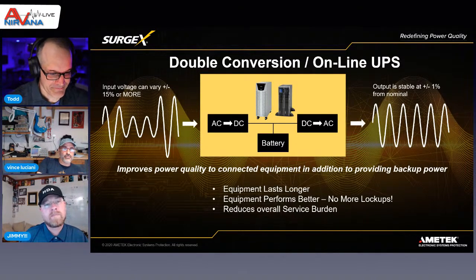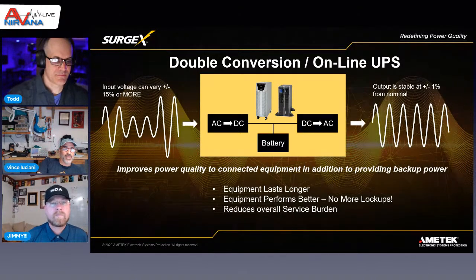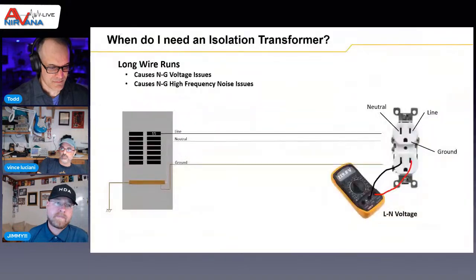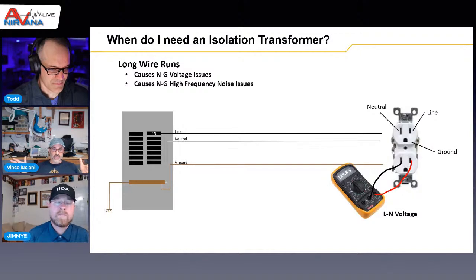But the one on the left, the white one, has internally what's called an isolation transformer. An isolation transformer is a wonderful tool to lower the noise floor. So not only is the UPS regenerating the power, giving you a very low distortion, highly regulated power signal, you are magnetically isolating it through the use of a transformer.